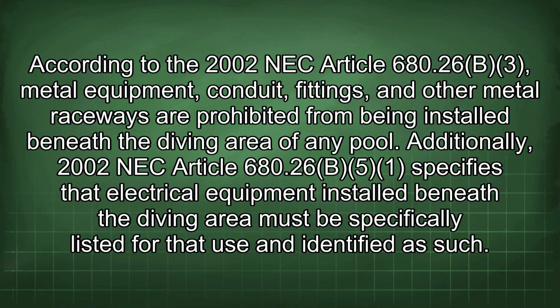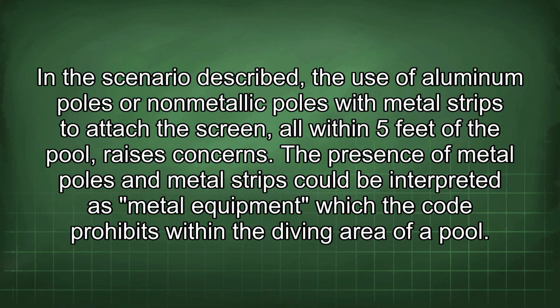680.26b3, metal equipment, conduit, fittings, and other metal raceways are prohibited from being installed beneath the diving area of any pool. Additionally, 2002 NEC Article 680.26b5 specifies that electrical equipment installed beneath the diving area must be specifically listed for that use and identified as such. In the scenario described, the use of aluminum poles or non-metallic poles with metal strips to attach the screen, all within 5 feet of the pool, raises concerns.